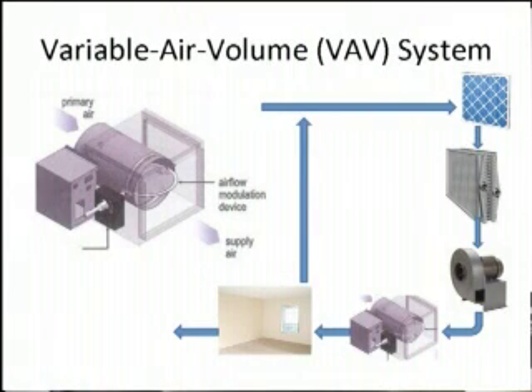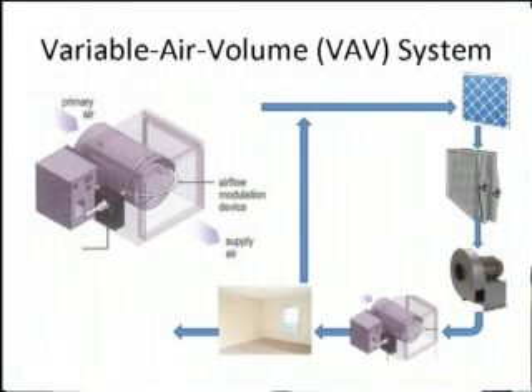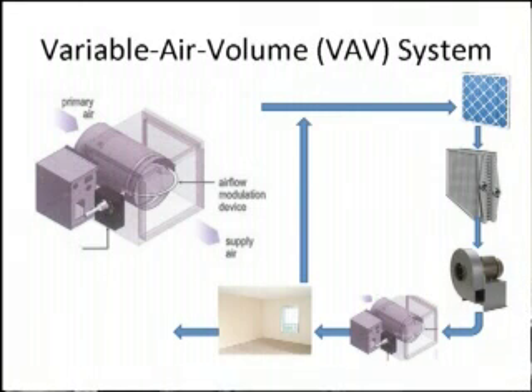This is a terminal unit inside of one of our buildings, and I just wanted to talk about the mindset, how I like to think about these things. I like to start at the very end of the thing and move backwards. So I go into a space that we've got a complaint about, and measure the parameters. If I've got a comfortable space, then we're done. If it's within the energy standards of the space temperatures, then we're done. If it's not, then I start looking at this guy here, the terminal box, at the very end of the equation, and try to optimize that thing as best we can.